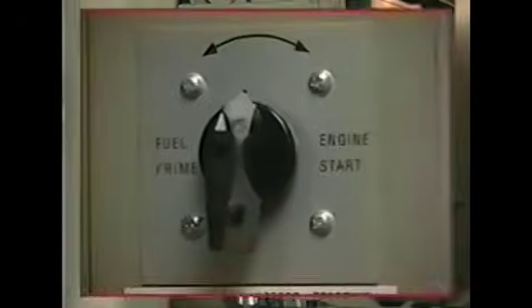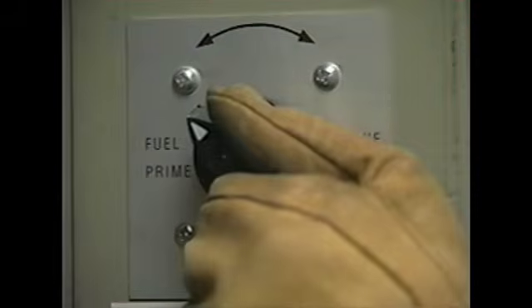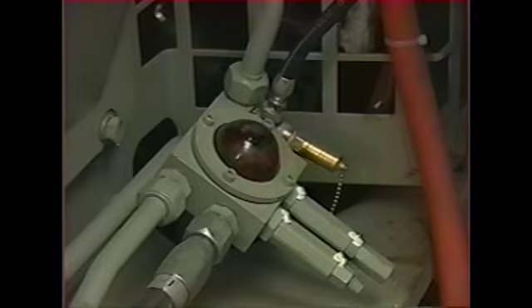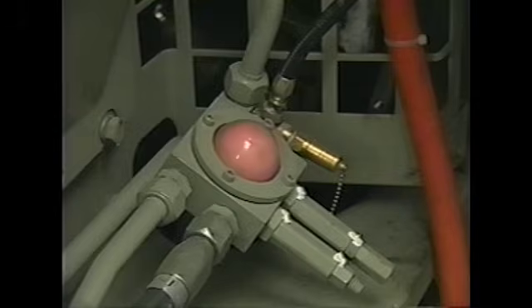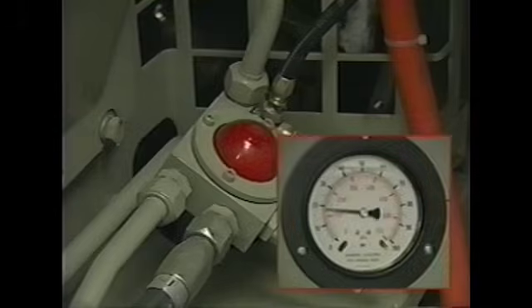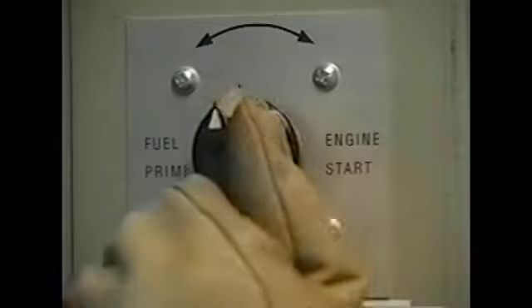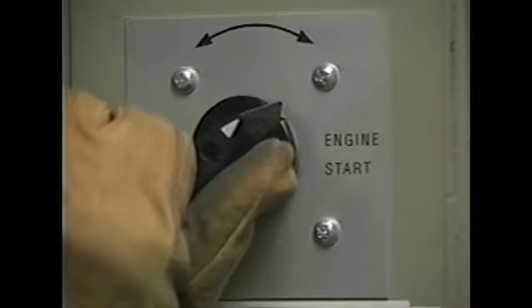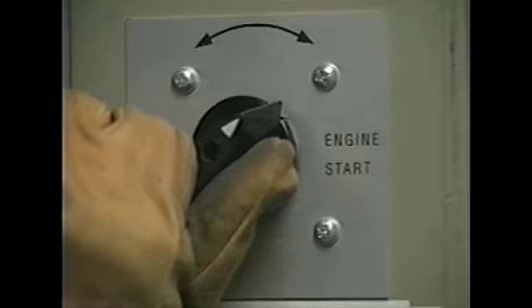Move the fuel prime engine start switch to the prime position. Observe the fuel flow sight glass to make sure it is free of bubbles. The fuel pressure should rise to about 55 psi. After the pressure stabilizes, move the switch to the start position. After a 3 to 5 second pause, the engine begins to rotate. Hold the switch in the start position until the engine is running.